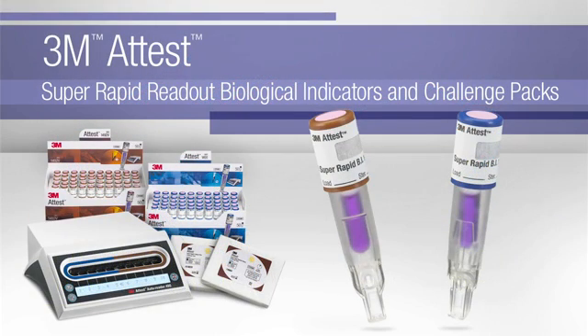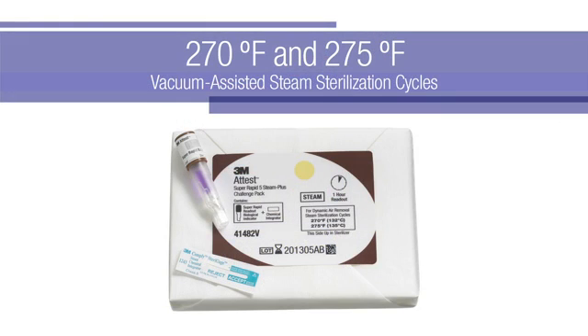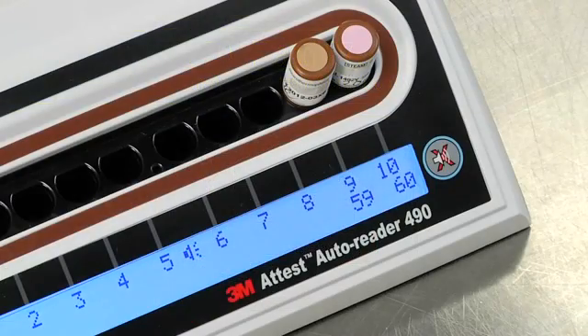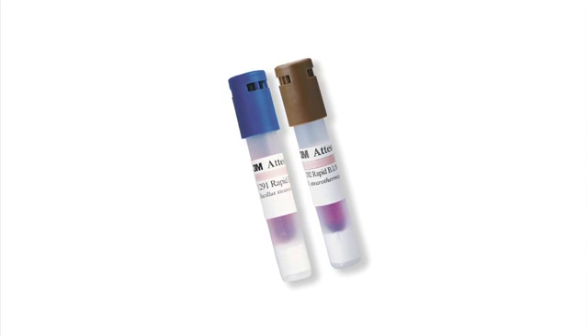The 3M Attest Super Rapid Readout Biological Indicator System includes biological indicators and challenge packs. 41482V Brown Cap BIs and associated challenge packs monitor 270-degree and 275-degree Fahrenheit vacuum-assisted steam sterilization cycles. The system also includes the 3M Attest Auto Reader 490, designed to incubate and automatically read the results of 3M Attest Super Rapid Readout BIs. Other biological indicators are not compatible and cannot be used with this auto-reader.